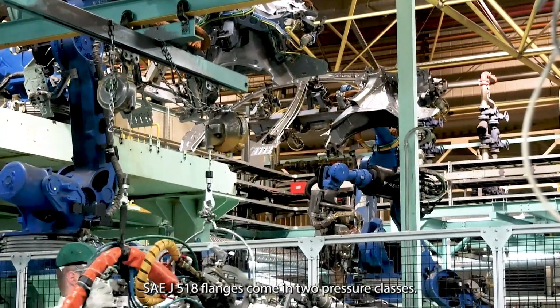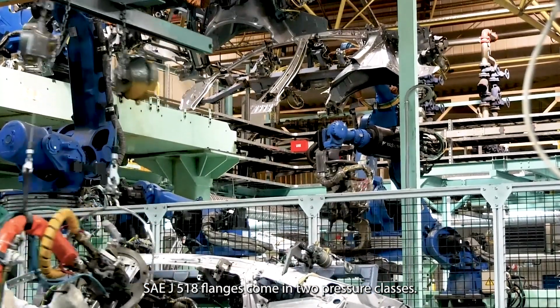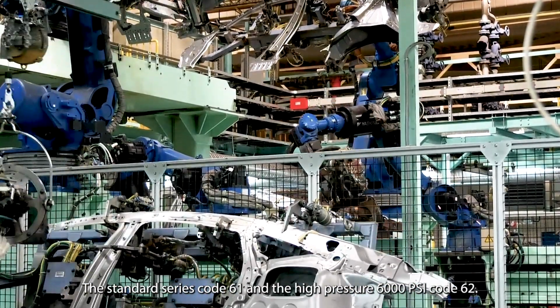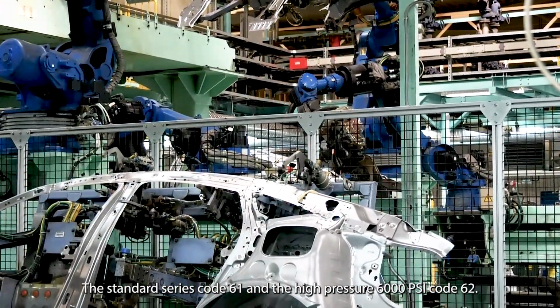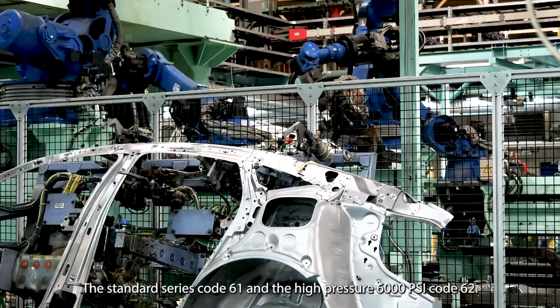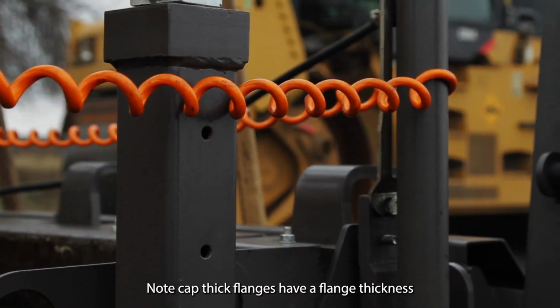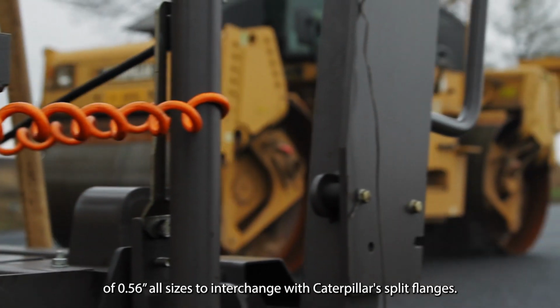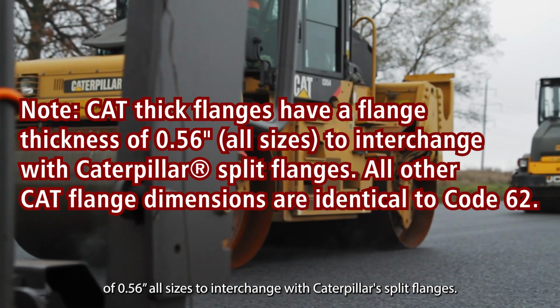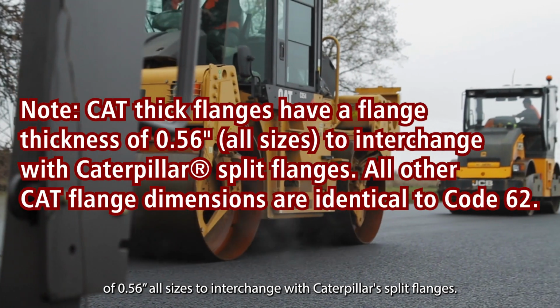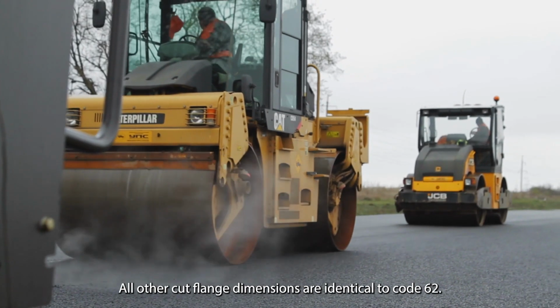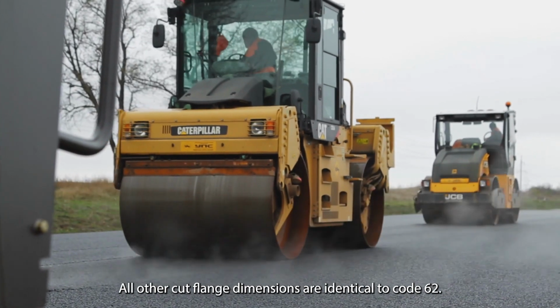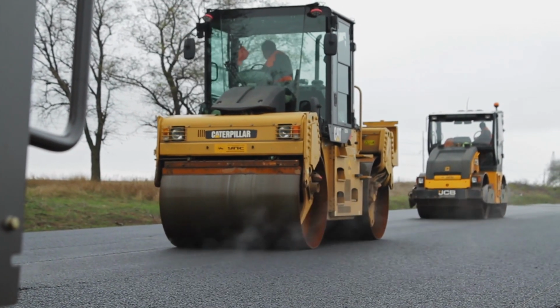ISO 6162 SAE J518 flanges come in 2 pressure classes: the standard series, code 61, and the high pressure, 6000 psi, code 62. Note: Cat-thick flanges have a flange thickness of 0.56 inch, all sizes, to interchange with Caterpillar split flanges. All other Cat flange dimensions are identical to code 62.